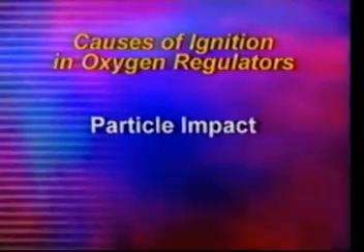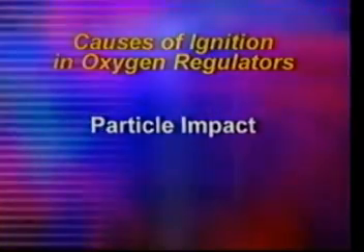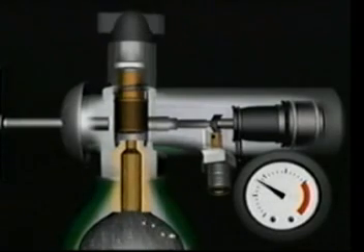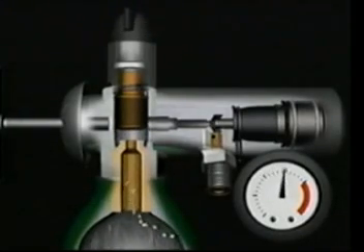One contributing factor is particle impact. This involves small particles that are generated during assembly. Over time, these particles can flake off from inside the cylinder. What happens is that these small particles can be caught up in the flowing oxygen and accelerated to a high velocity.